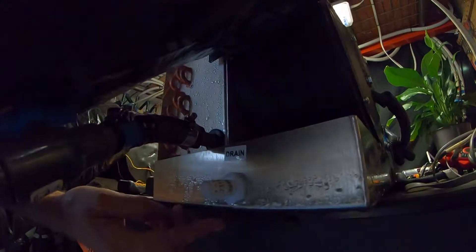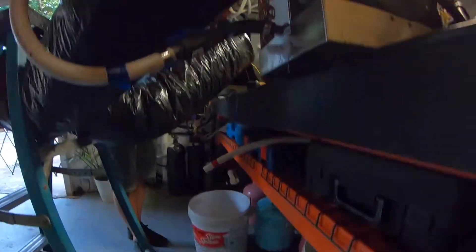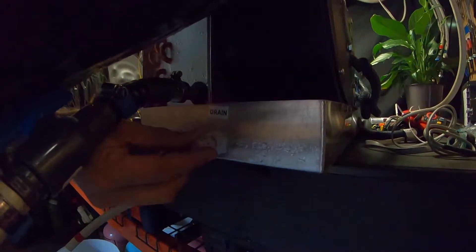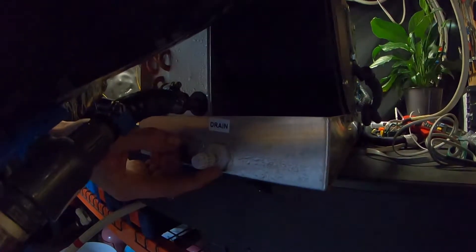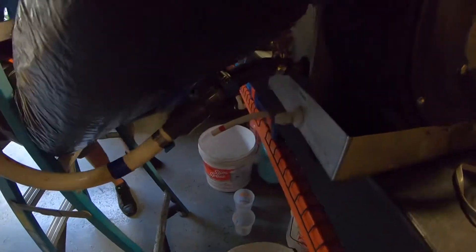If you look at the competitor system over here, number one, it's a bit higher than where ours is, so we tend to have a lot more sitting water in the drain pan of the unit. We have to give it a lot of angle. Number two is that you typically need to have a nut on the other side of the fitting. Putting a nut in there tends to be a bit more complicated on the installation side.